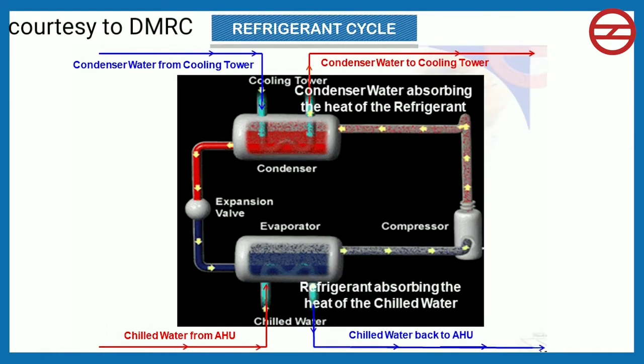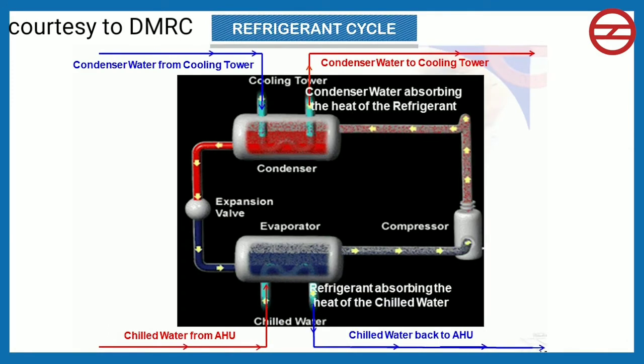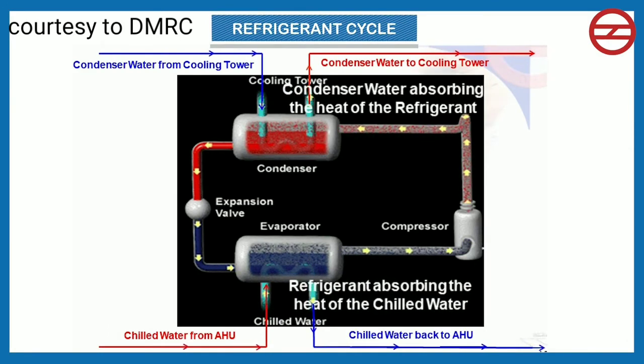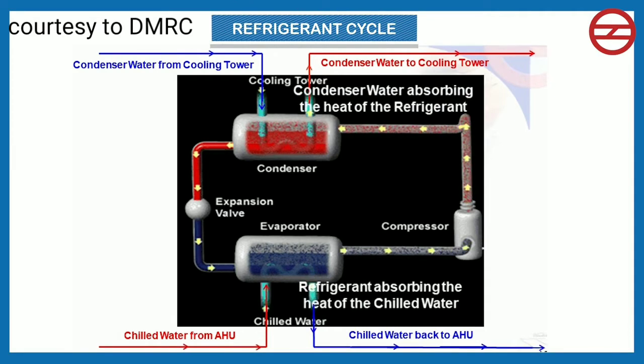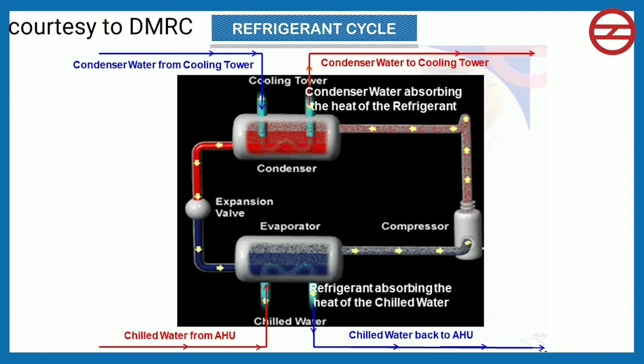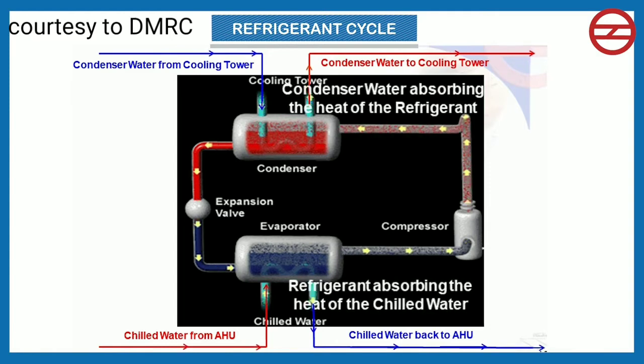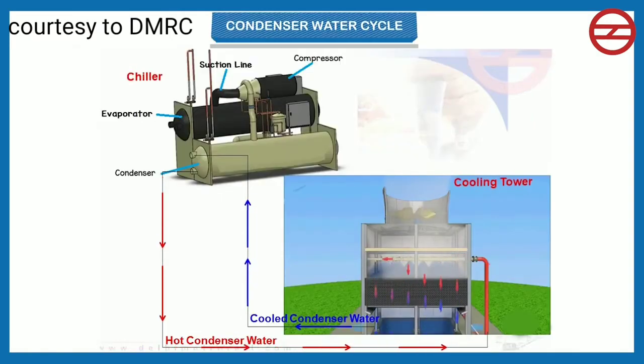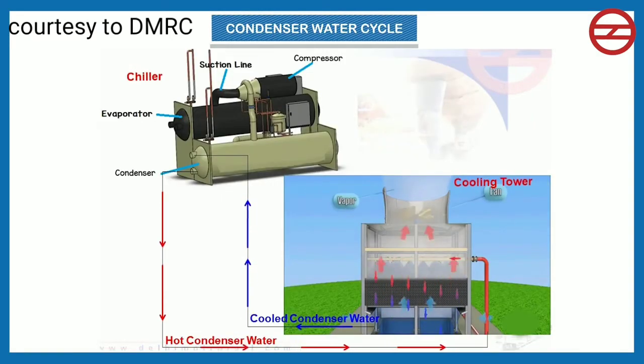Second is the refrigerant cycle. In this cycle, refrigerant is continuously absorbing heat of the chilled water in the chiller's evaporator and rejecting its heat to the condenser water in the chiller's condenser. And third is the condenser water cycle. In this cycle, condenser water is continuously supplied by cooling tower. This condenser water absorbs the heat of the refrigerant in chiller's condenser and returns to the cooling tower.